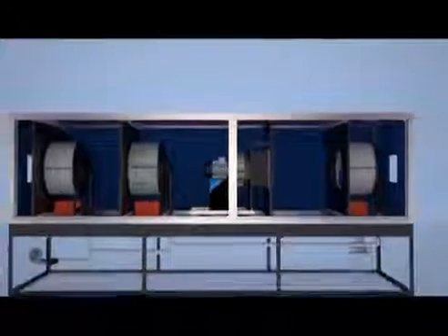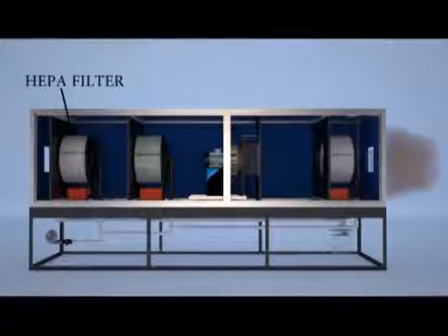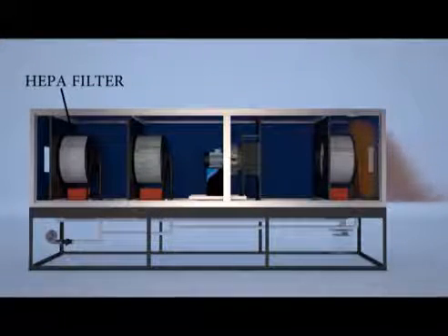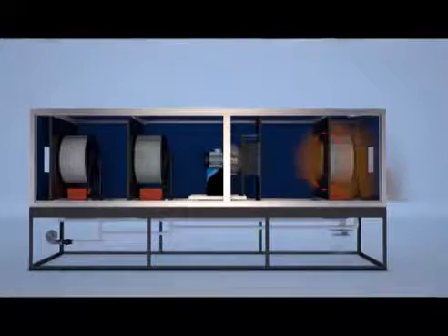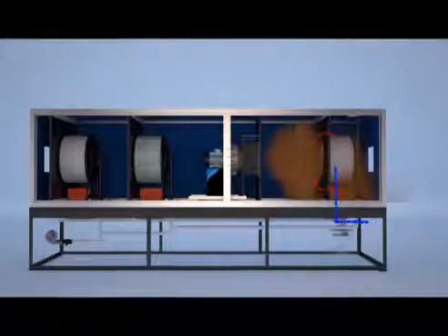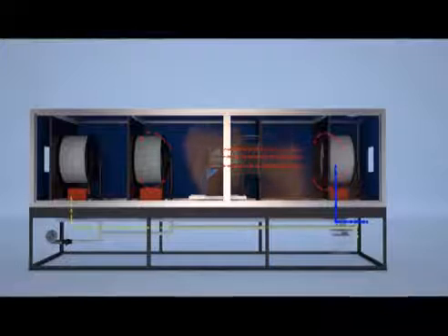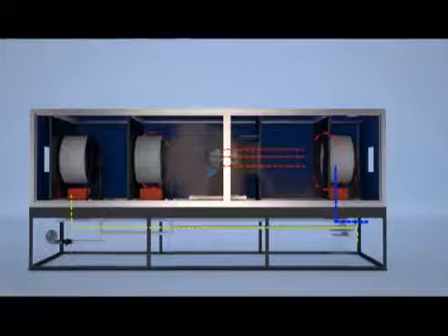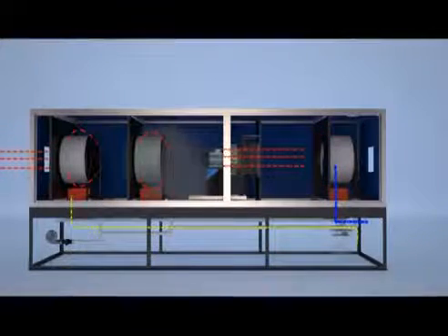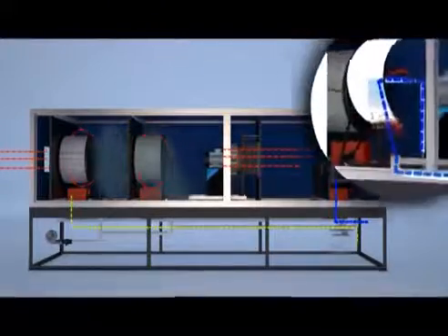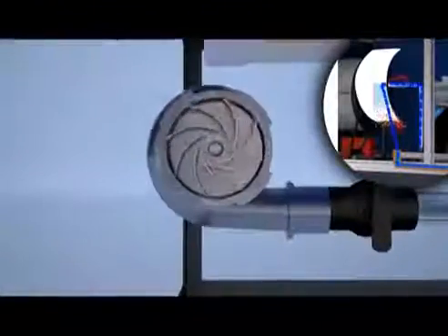The air passes through the outer periphery of the filter to the inside, and the remaining parts on all sides of the filter are closed and sealed. The air passes through only the outer periphery. The dust particles remain on the outer side of the filters, which rotate and come to the downside. There is a provision inside the filter to blow off filtered air by a blower at precise velocity and precise pressure.